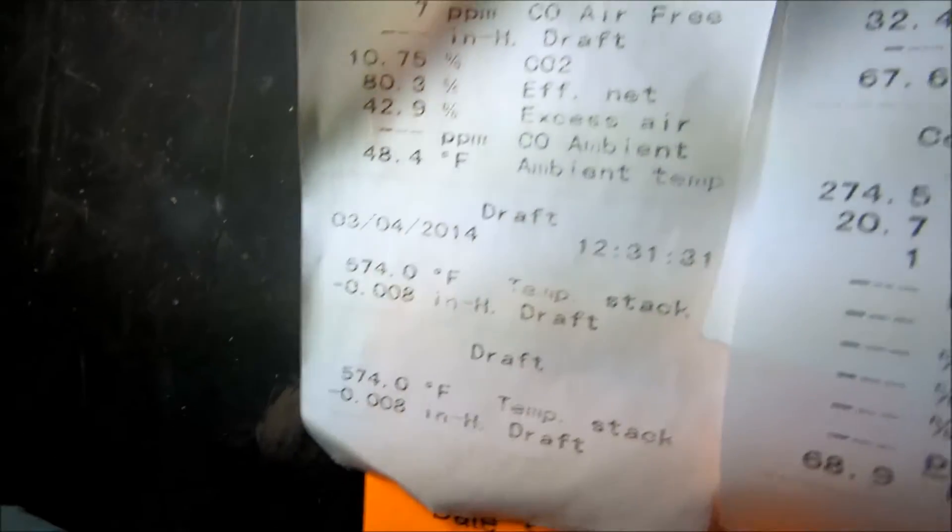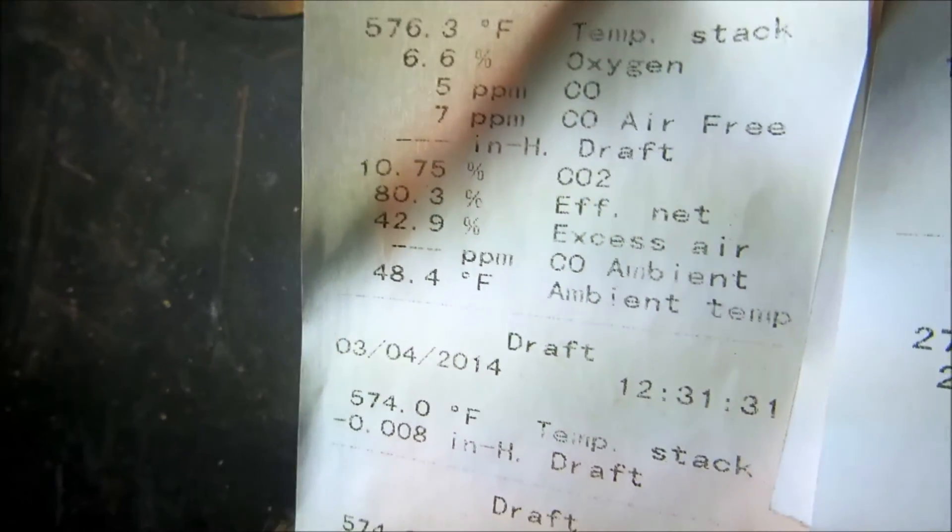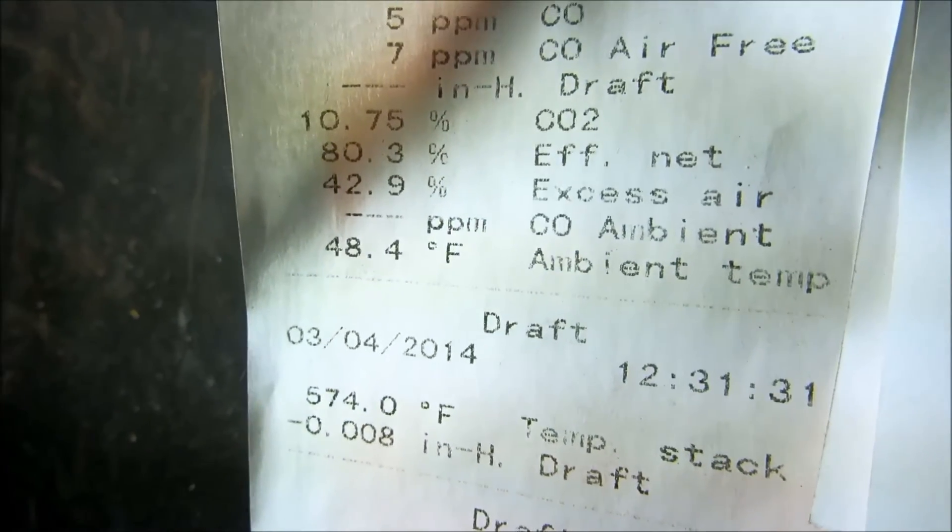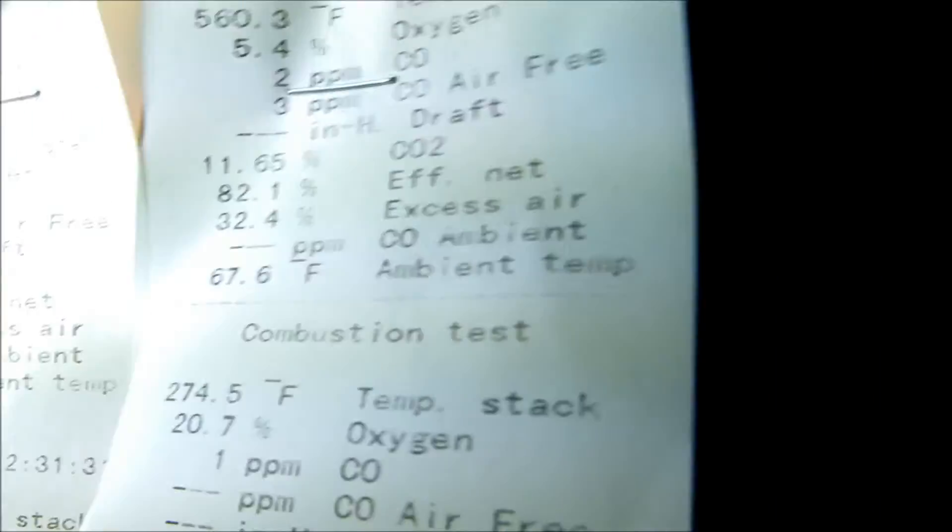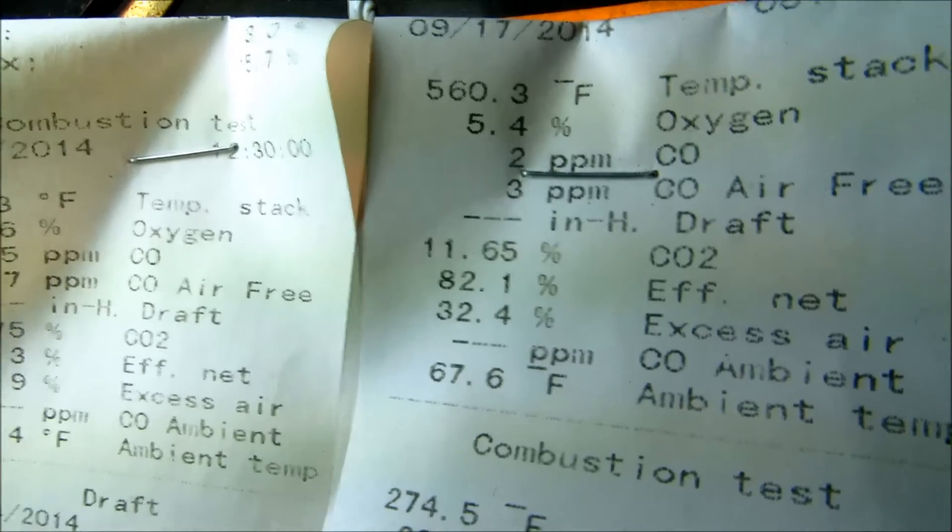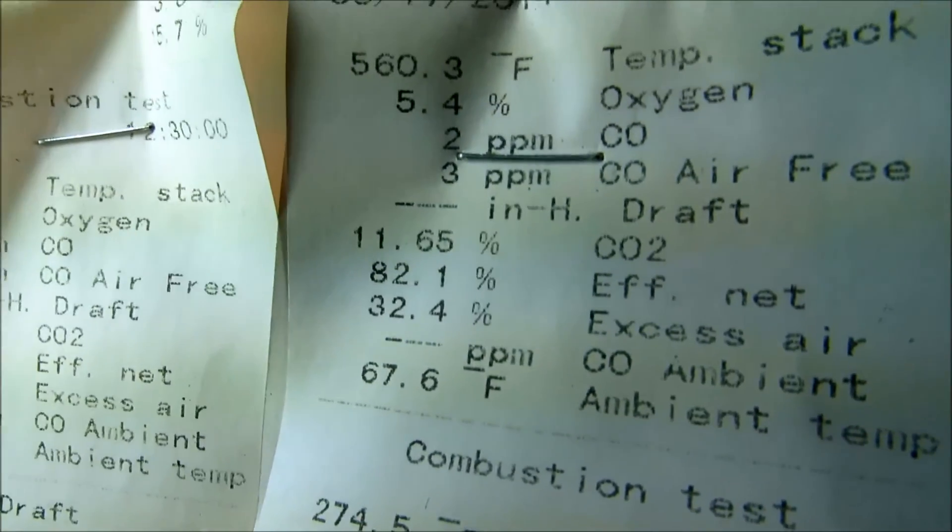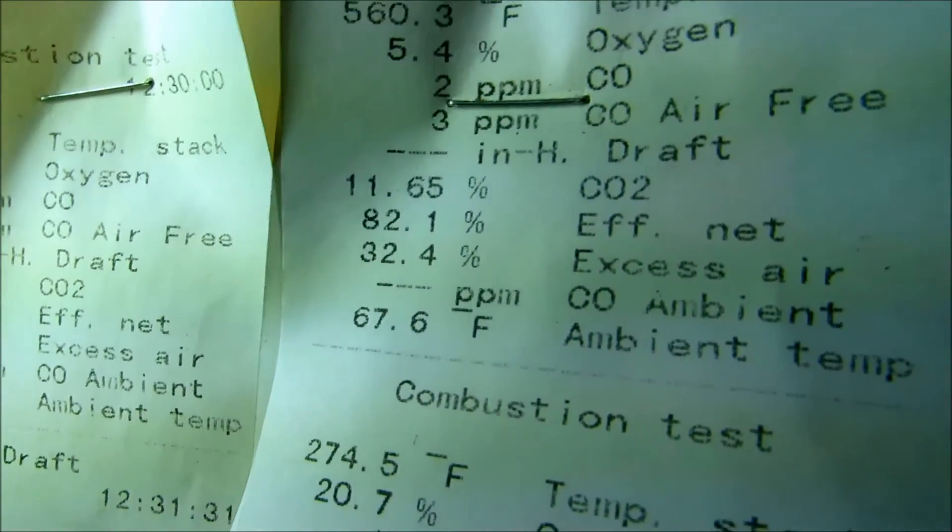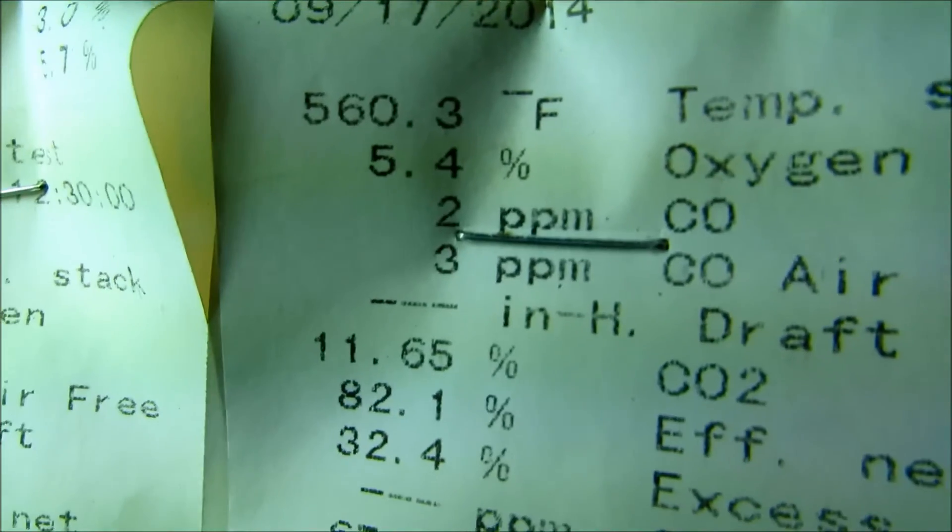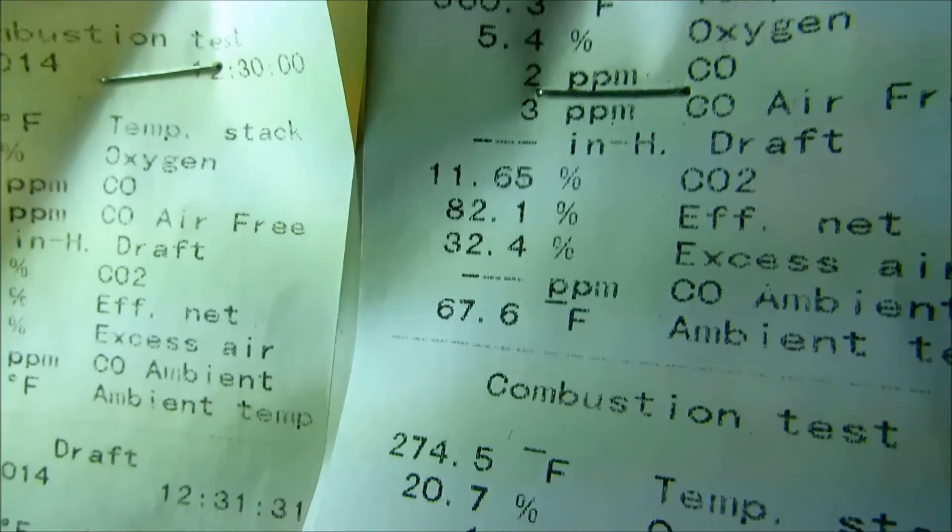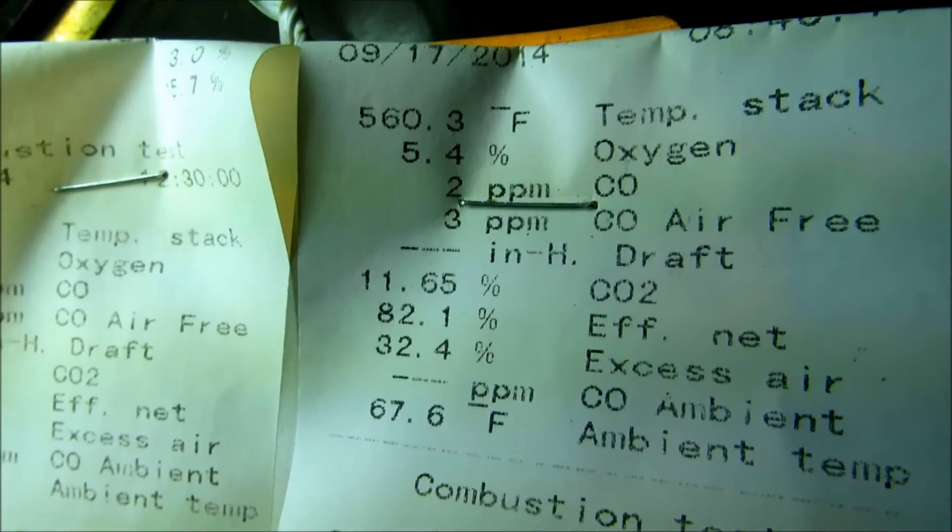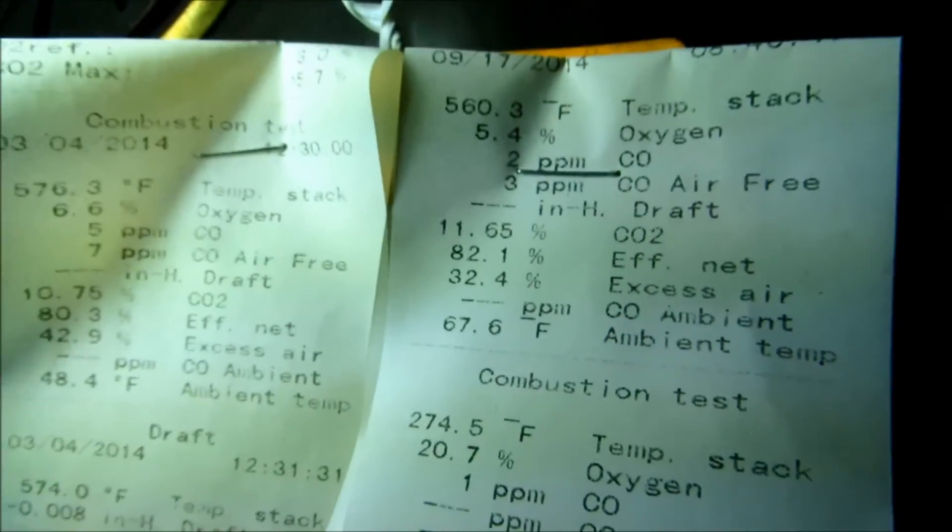Alright, last time I was here I had my CO2 at 10.75 and my parts per million was 5, and I was 80.3% efficient. I was running it lean. Now this time I brought it close to 12 - 11.65 on the CO2. Efficiency went up to 82%, and parts per million went down to 2. So it's running cleaner and better now with a little bit higher CO2.